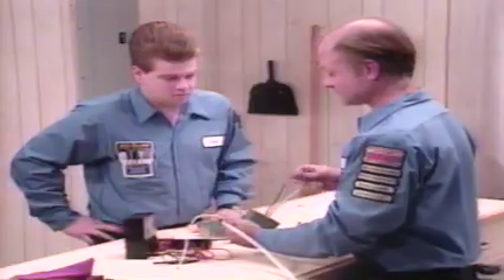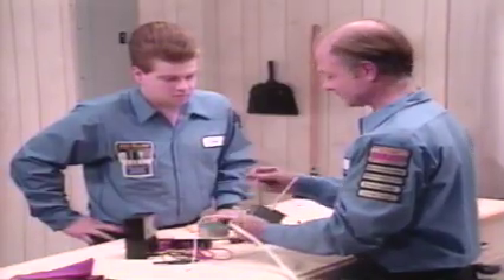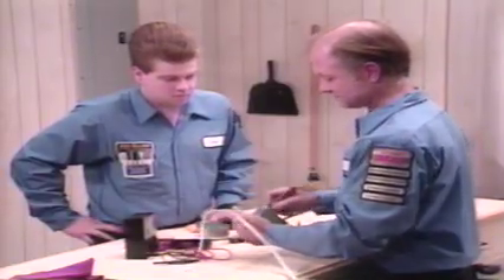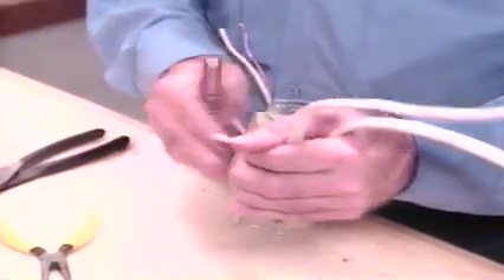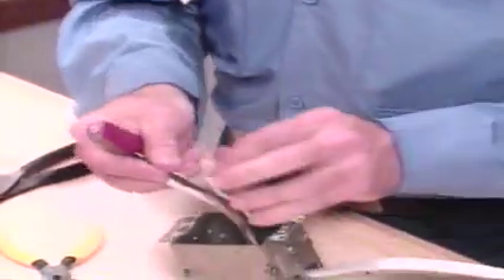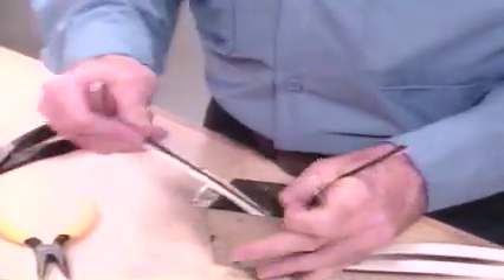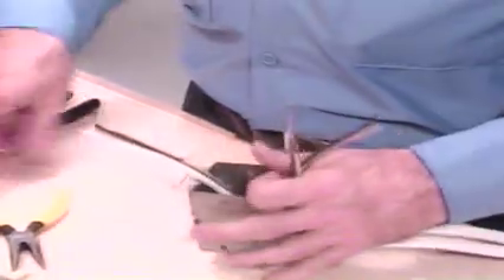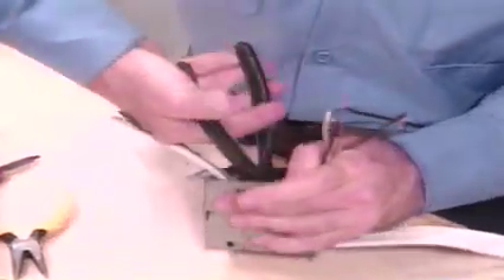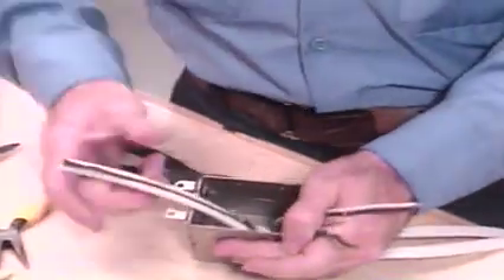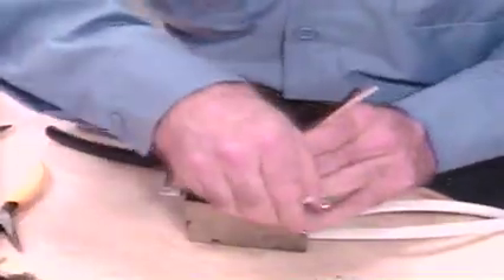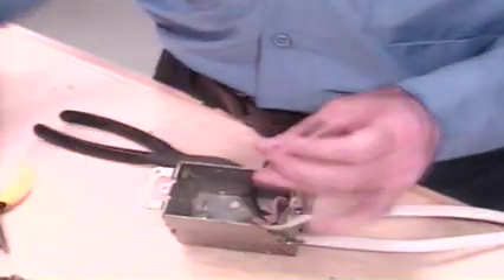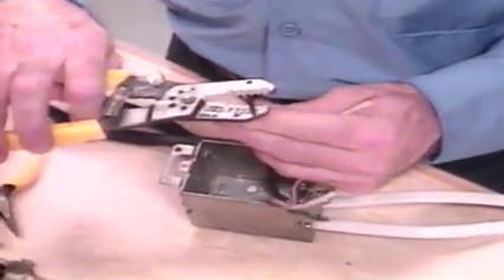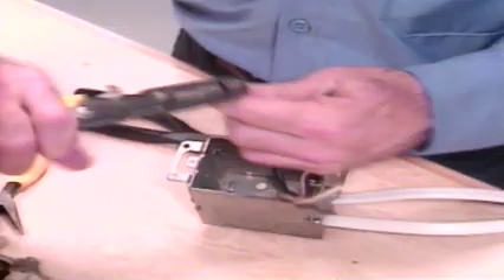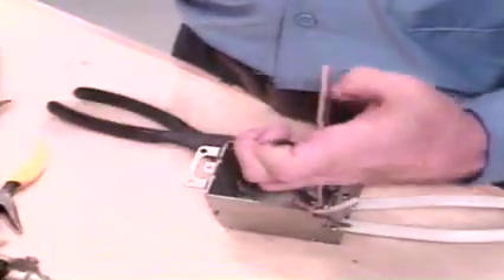Now, we've got the wires already coming into the box. First thing we want to do is cut off about 8 inches of the sheathing. I've already cut off one. Okay. Pull it all the way back along with the paper. Just cut it off. All right. Then you match the wire gauge on the stripper to the wire you're using and strip back about 3/4 of an inch.